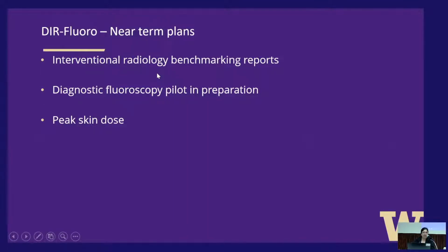There's very little information in the literature on benchmarking. There is some, but it's not very modern fluoroscopy. So I think this will really help us all moving forward. So this is for interventional. DIR is also looking at diagnostic fluoroscopy, things like you do in an RF room, for GI and GU cases. And then, of course, having calculation of peak skin dose.